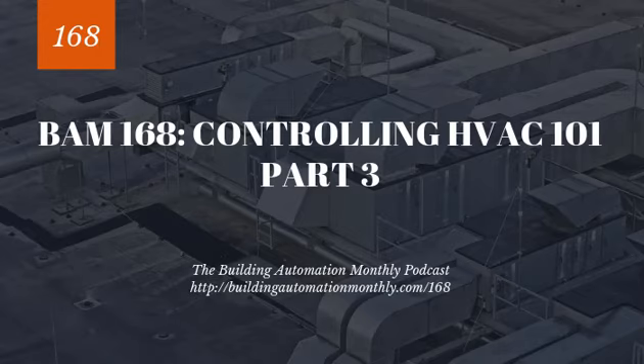So the last thing I want to discuss is variable speed drives, which are basically like fire rates for chillers. If we think of boilers having adjustable fire rates, chillers vary the speed of refrigerant flow using variable speed drives. When you vary the speed of refrigerant flow, you're varying the amount of heat that is absorbed and exhausted from the building's chilled water return out to the condenser water supply and then through the cooling tower loop.